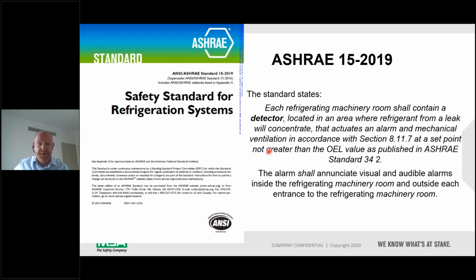Then we have ASHRAE 15, which is a standard used quite a lot where I am in the Middle East, in Dubai, for a lot of the plant rooms. It says that if there is a refrigerant in a refrigerating machinery room, a detector must be installed. It highlights a lot of other things in terms of self-contained breathing apparatus, and the alarm needs to be visual and audible both inside and outside the room. A lot of the specifications we get in the Middle East just say that the refrigeration room must comply with ASHRAE 15. Then we know we need to put some kind of refrigerant detector in that room to detect leakage of the gas from the chiller.